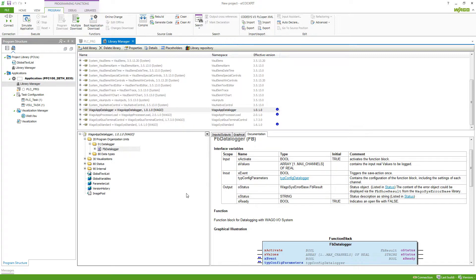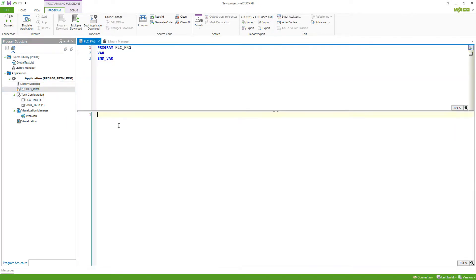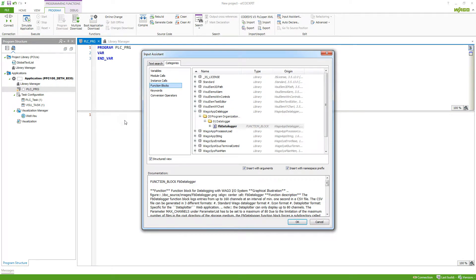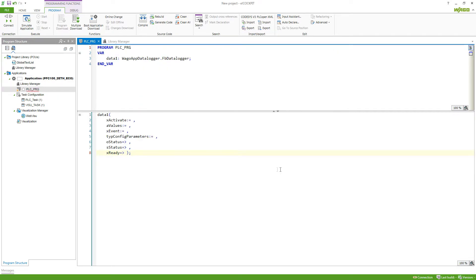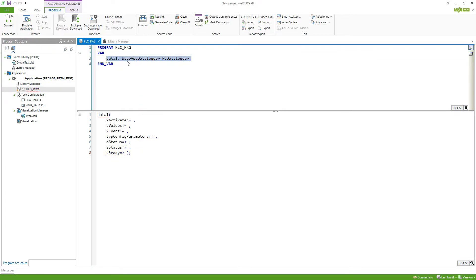If we want to add a function block from a library into our project, we just go to the project, hit F2 to bring up the input assistant, and then we will find it under the category function blocks inside of the library. We can select it, hit OK, define a name, and hit OK. Now we create an instance of the function block, so here our WAGO data logger FB data logger and the ins and outputs in the corresponding language into your program.